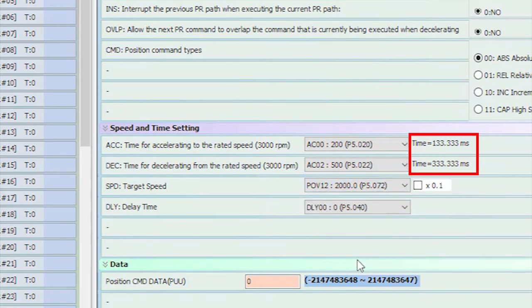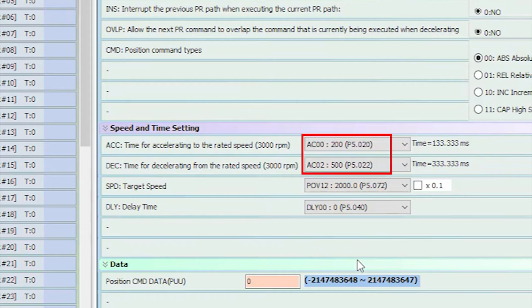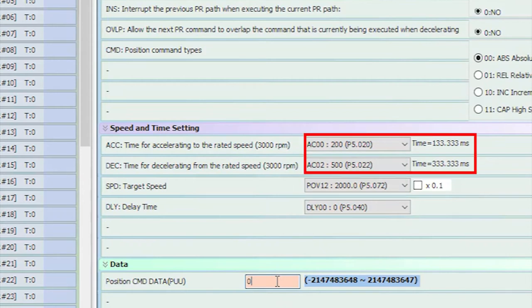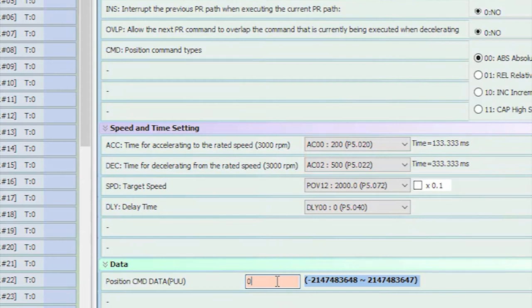Now did you see the ramp time change? Remember, the ramp times selected are the time to go from 0 to full rated speed, which for this drive is 3000 RPM. Since we are only going to 2000 RPM, or two thirds of the way, the acceleration time is two thirds of the total. I love that the SureServo2 software calculates that for me.